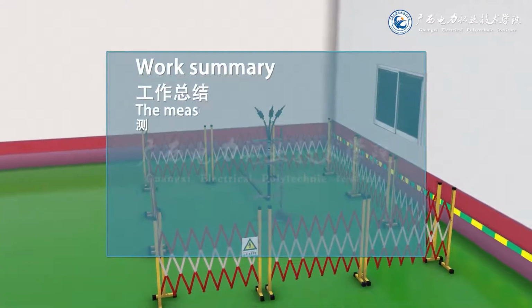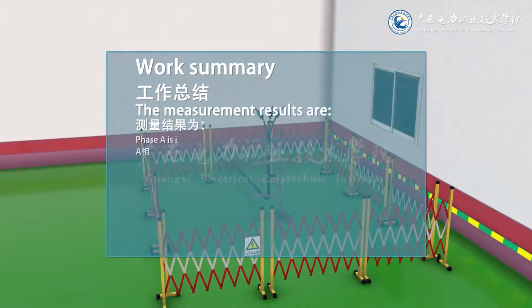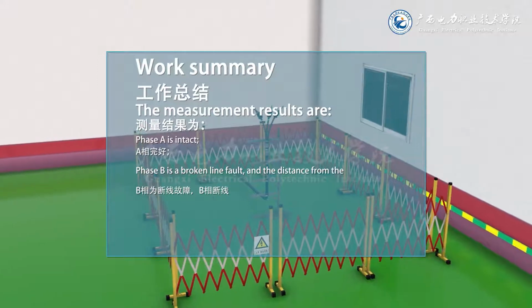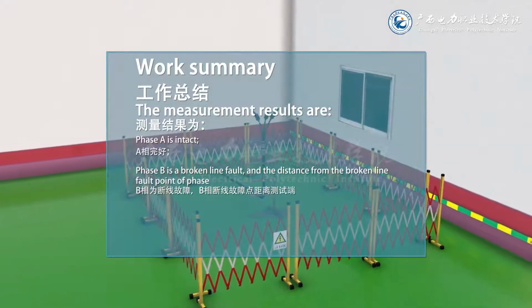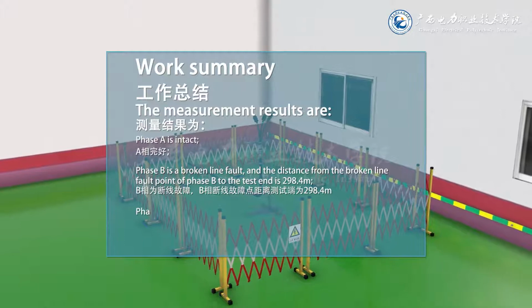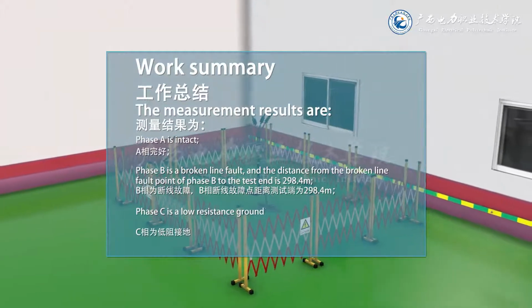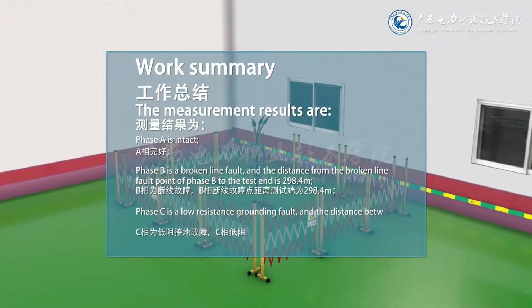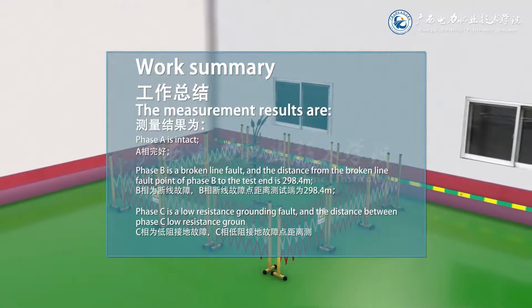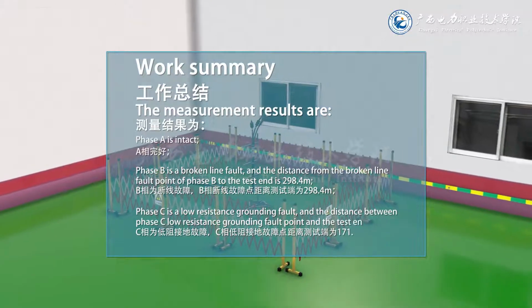Work summary. The measurement results are: phase A is intact, phase B has a broken-line fault, and the distance from the phase B broken-line fault point to the test end is 298.4 meters. Phase C has a low-resistance grounding fault, and the distance between the phase C low-resistance grounding fault point and the test end is 171.7 meters.